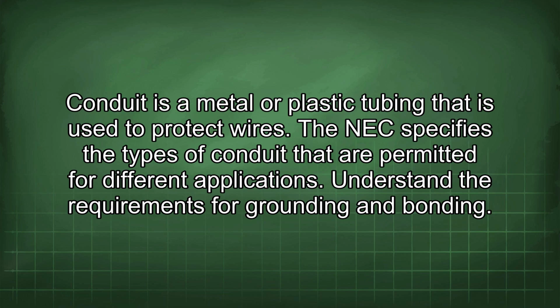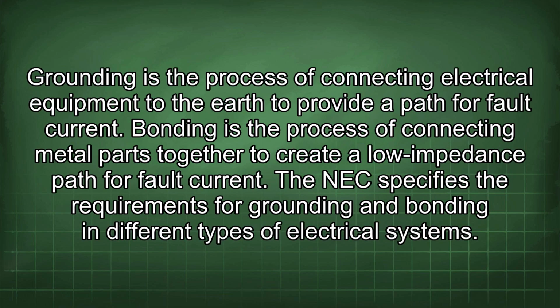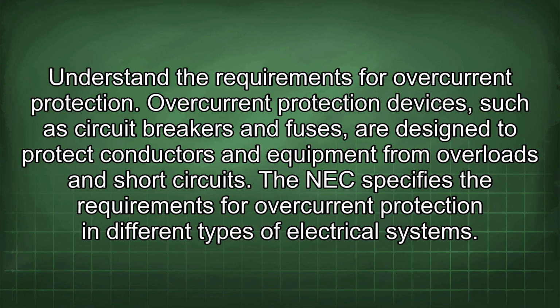Understand the requirements for grounding and bonding. Grounding is the process of connecting electrical equipment to the earth to provide a path for fault current. Bonding is the process of connecting metal parts together to create a low impedance path for fault current. The NEC specifies the requirements for grounding and bonding in different types of electrical systems. Understand the requirements for overcurrent protection. Overcurrent protection devices, such as circuit breakers and fuses, are designed to protect conductors and equipment from overloads and short circuits. The NEC specifies the requirements for overcurrent protection in different types of electrical systems.